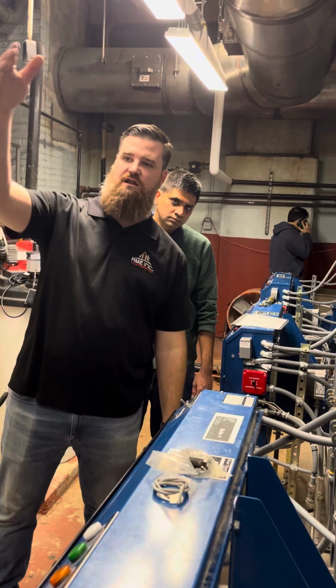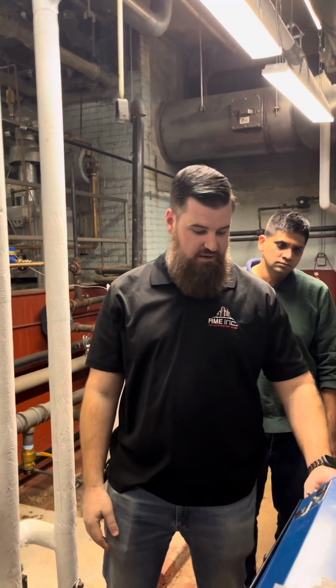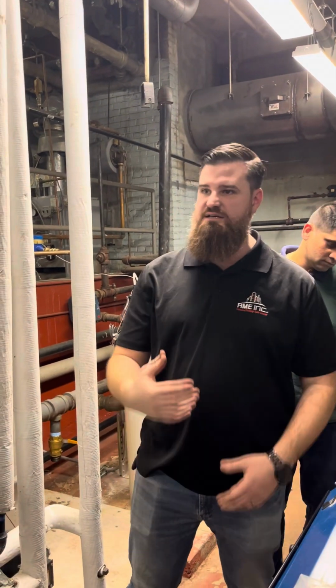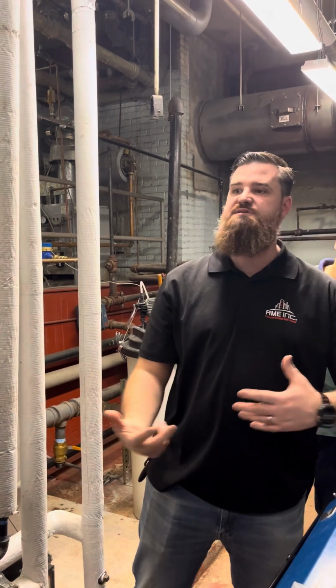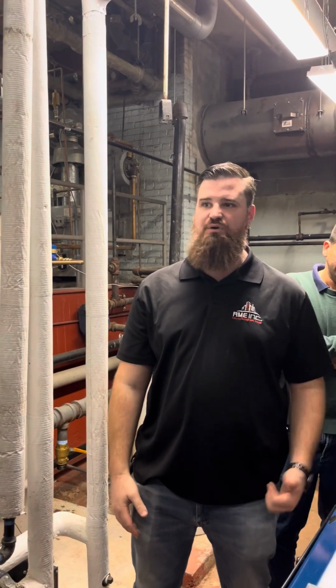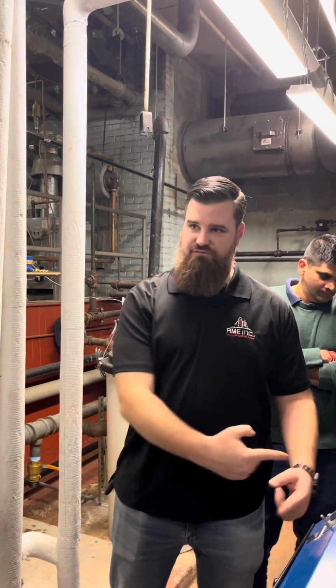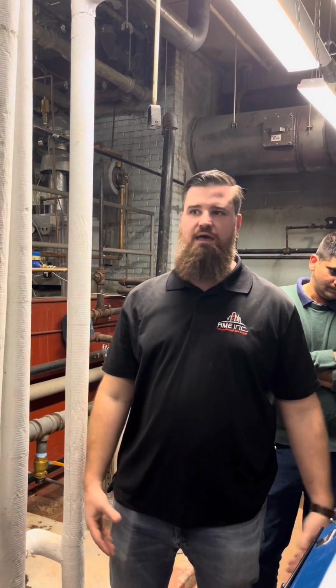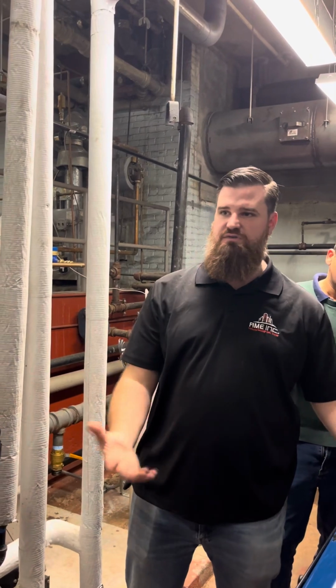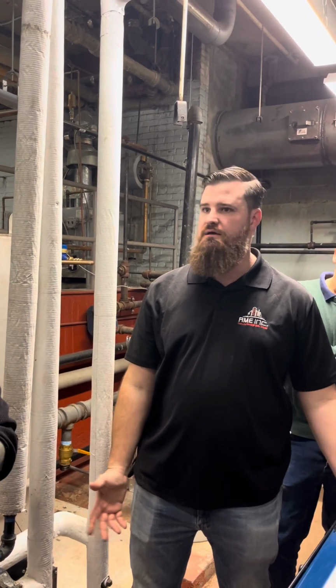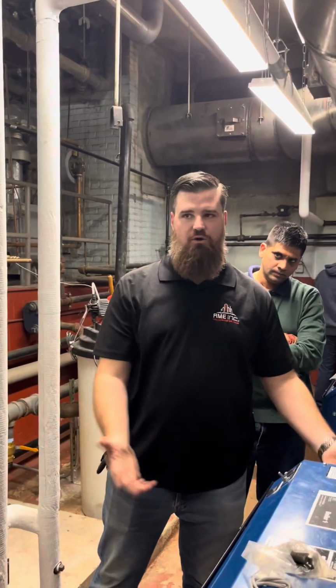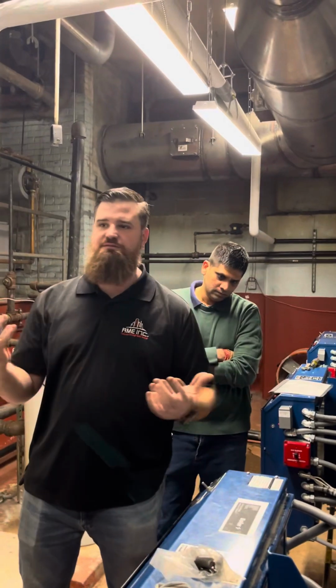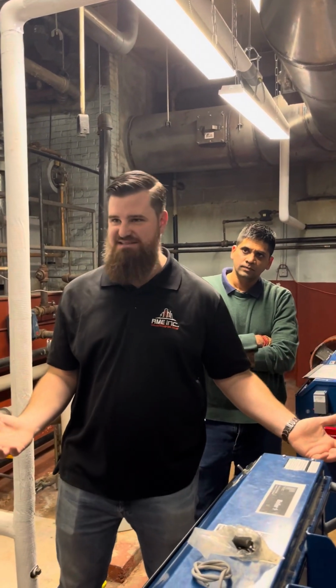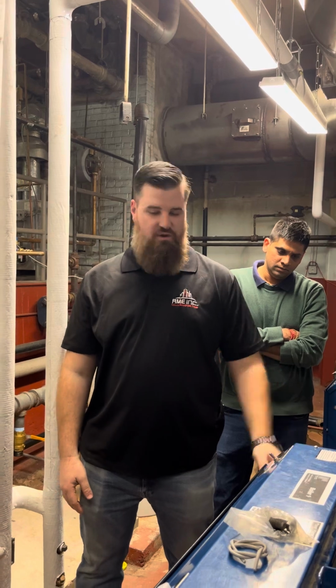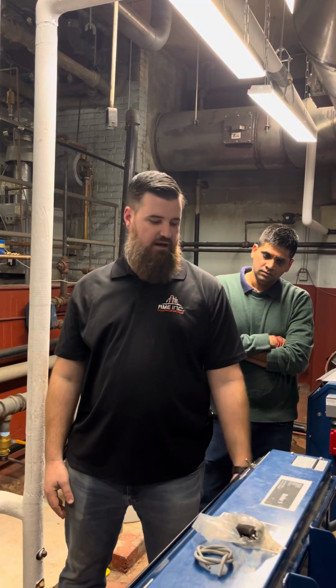You get a boiler operator in here. Sometimes they'll come in here and they'll flip this over to close because they want it to run as if it was in auto. They may forget to put this back, and you're finding that this boiler is running when it's not supposed to be. That's the first thing to check. Happens all the time. Guys forget to put these back in auto all the time. It is what it is. I forget to put things back in auto, and I'm the guy who operates these things every day, okay? So just always make sure that's the first thing I would check, it's in auto, okay?